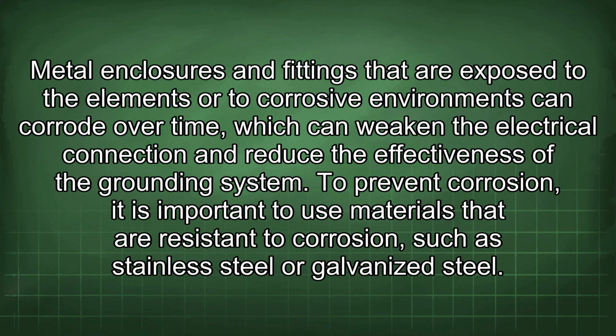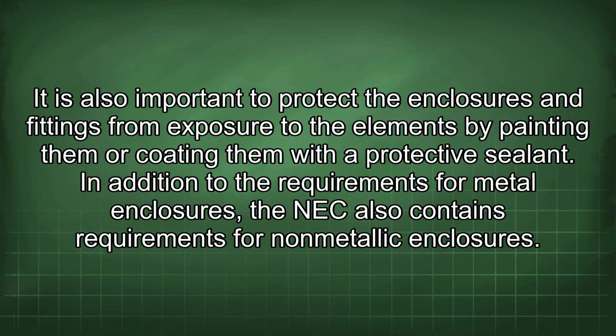Metal enclosures and fittings that are exposed to the elements or to corrosive environments can corrode over time, which can weaken the electrical connection and reduce the effectiveness of the grounding system. To prevent corrosion, it is important to use materials that are resistant to corrosion, such as stainless steel or galvanized steel. It is also important to protect the enclosures and fittings from exposure to the elements by painting them or coating them with a protective sealant.